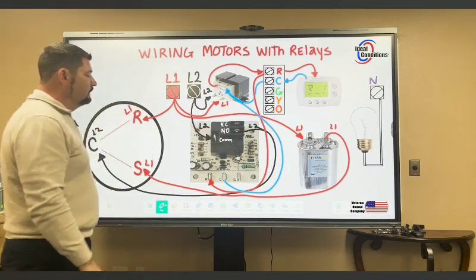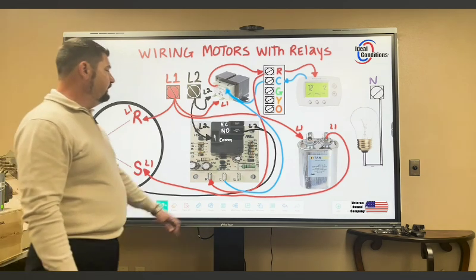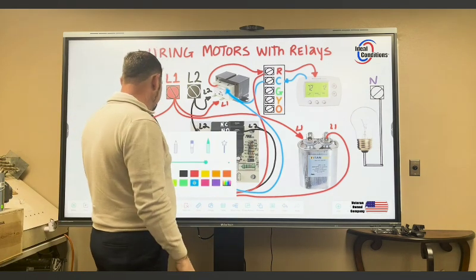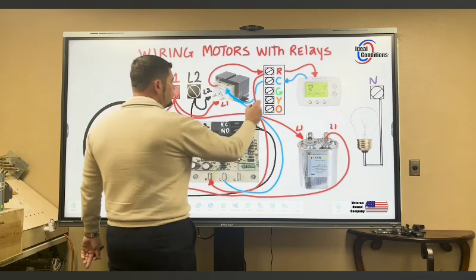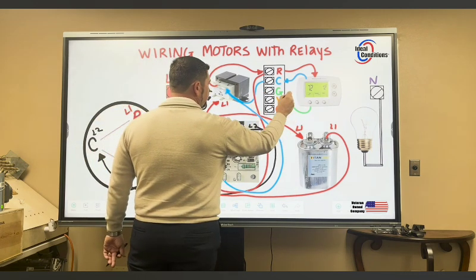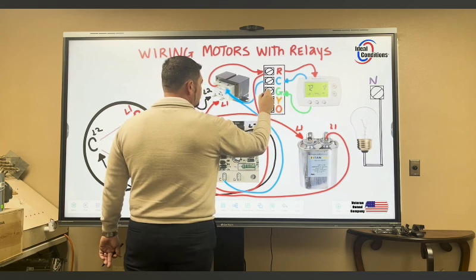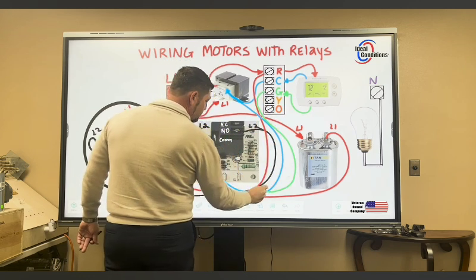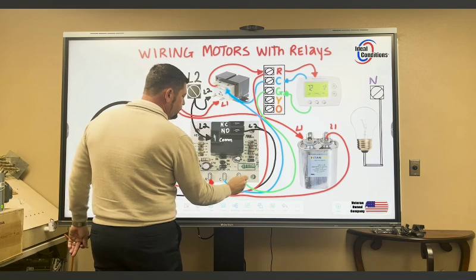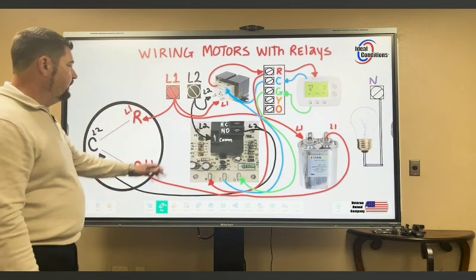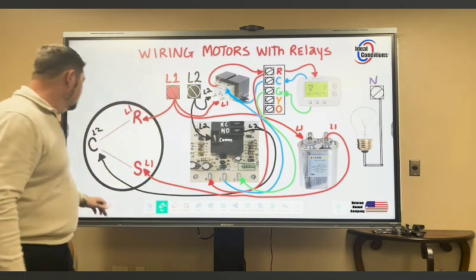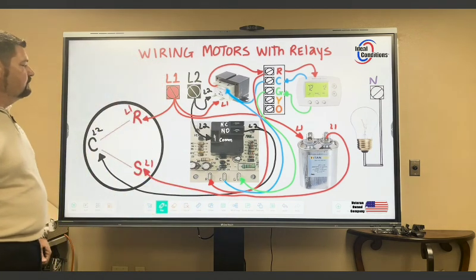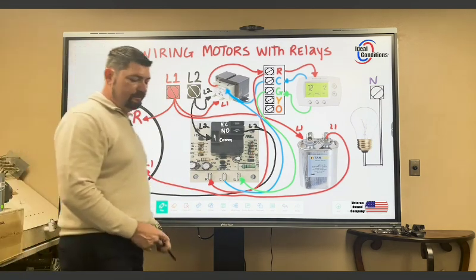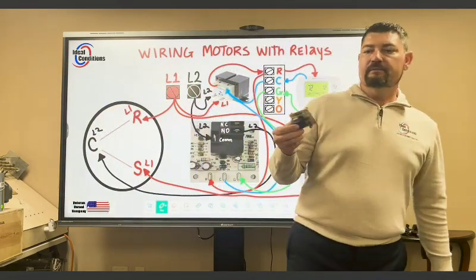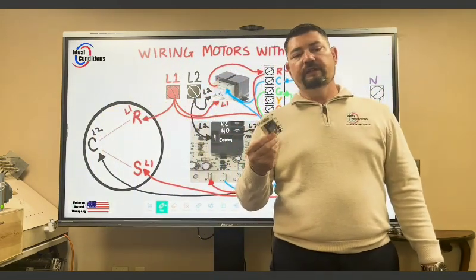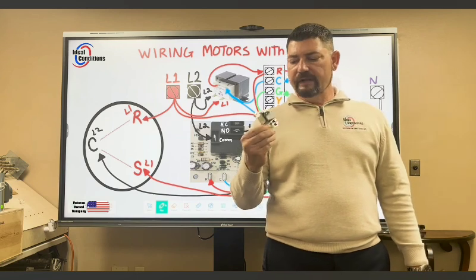There we go. The only thing we're missing is the G. We're going to go ahead and give it a G call. That's going to come from the thermostat. Add a G on the terminal block. We're going to come over to our blower control board as an input. And now L2 will be for sure present here and energize the motor. It's very simple to wire this ICM255 blower control board. Very easy to wire this up.